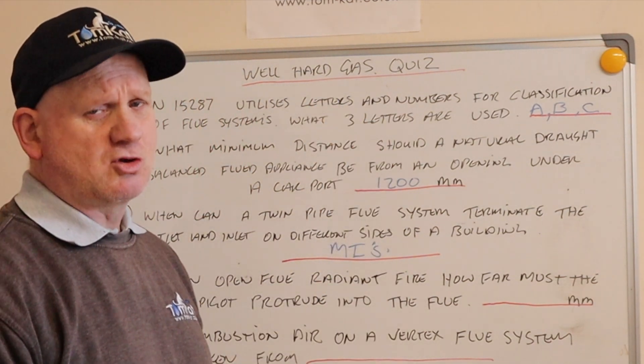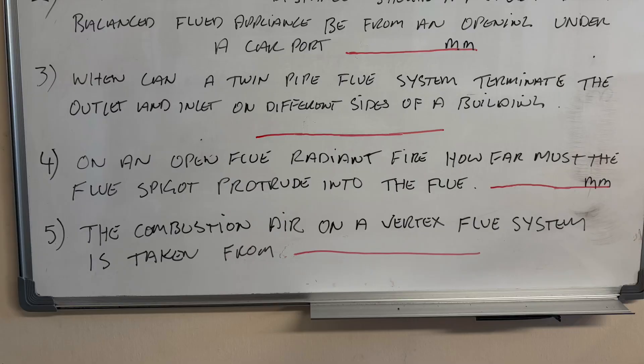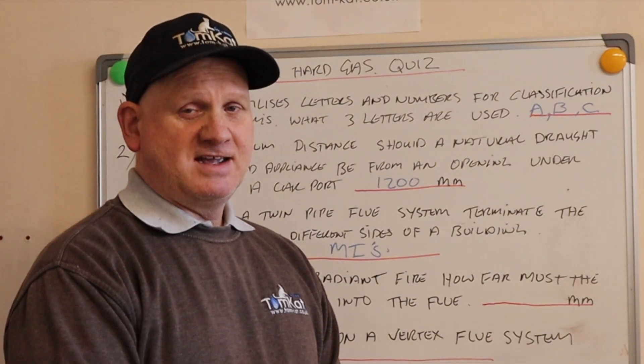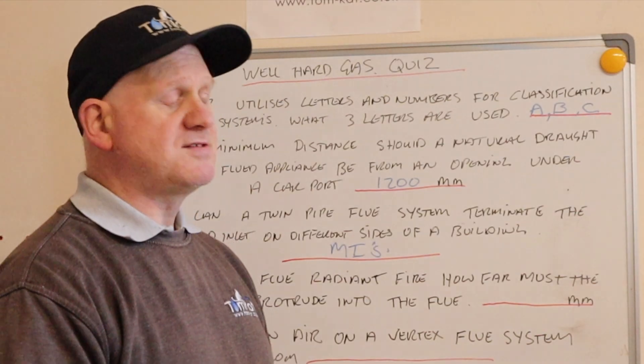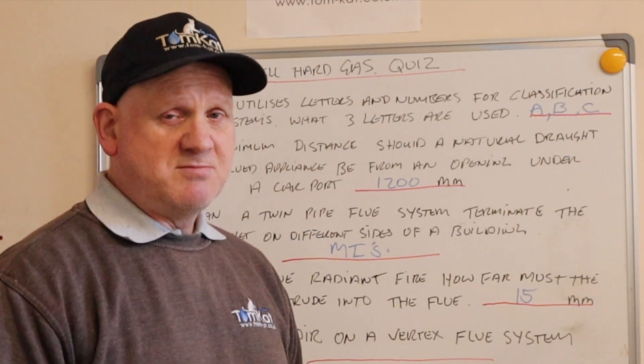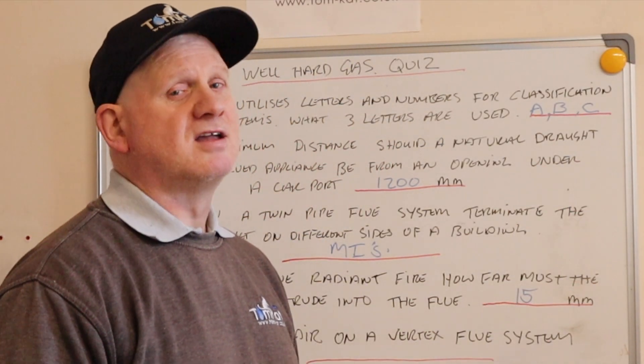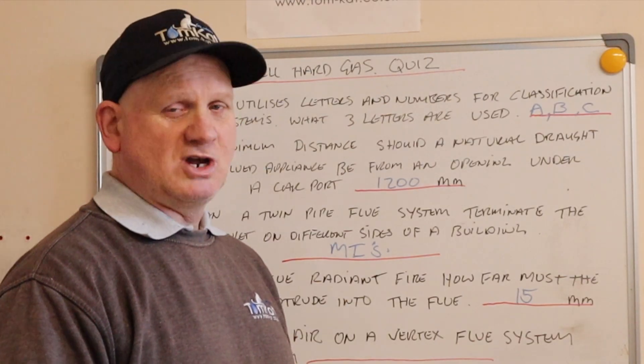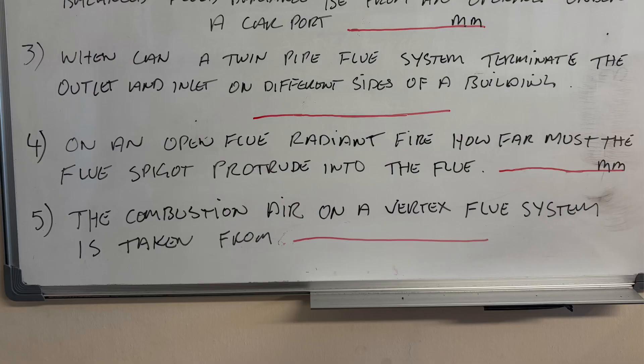Question number four: on an open flued radiant fire, how far must the flue spigot protrude into the flue? Hopefully you said 15 millimeters.